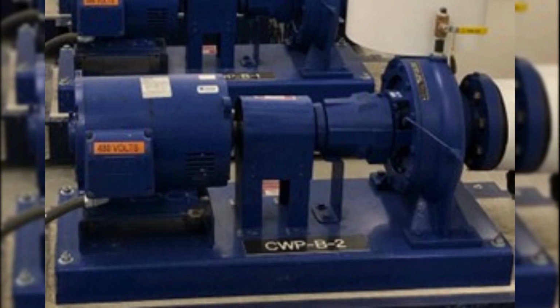But more importantly, SCA has moved toward variable speed packaged pumping systems. These are complete, factory-assembled skids that come with pumps, motors, VFDs, valves, strainers, sensors, and controls, all built onto a structural steel inertia base with vibration isolation. Now, why packaged pumping? It's about efficiency, integration, and reliability. With VFDs and BACnet controls built in, these systems communicate directly with the building automation system, giving facility operators visibility into pressures, flow, pump status, and alarms.